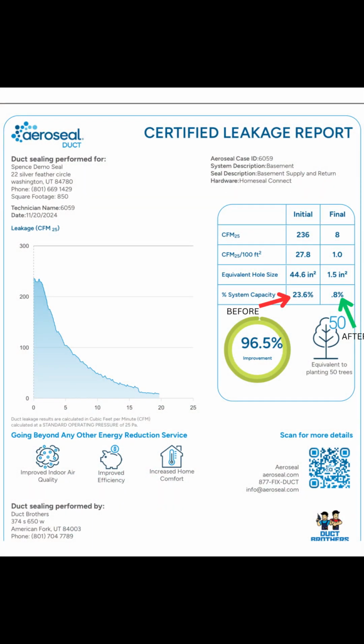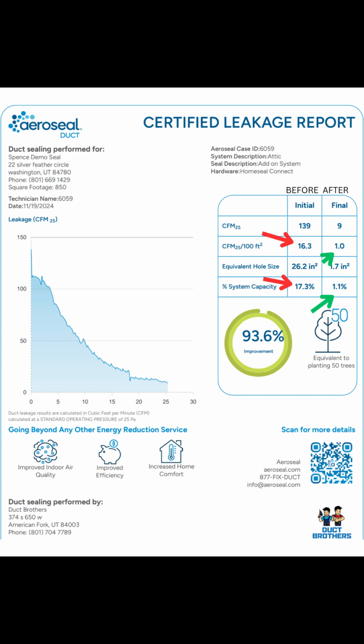On the pre-test, this system was losing 23.6% of its air, and we sealed it down to just losing 0.8%. The system upstairs started at 17.3% loss, and we sealed it down to just 1.1%. This home will now see significant energy savings and increased comfort.